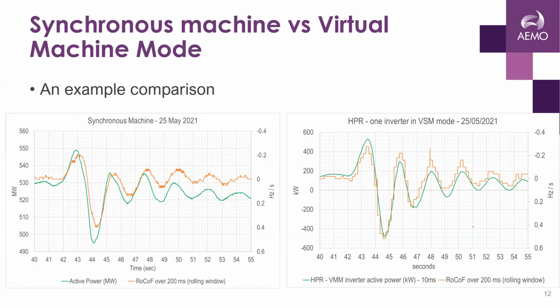This is the response from a synchronous machine, a large synchronous machine. On the primary axis is the megawatt, on the secondary axis is rate of change of frequency—again I have inverted it, so when it's going up, in reality the RoCoF is in the negative direction. You can see the response from the synchronous machine: when the rate of change of frequency is high, you get more megawatt; as the rate of change of frequency decreases, you get less megawatt, and eventually the governor kicks in and drives the response.